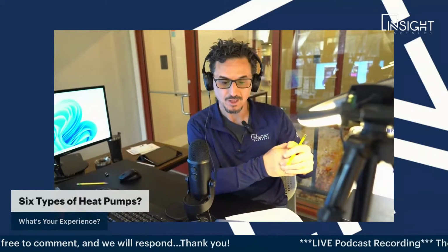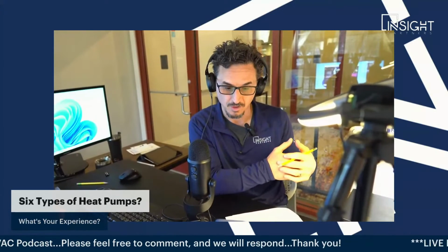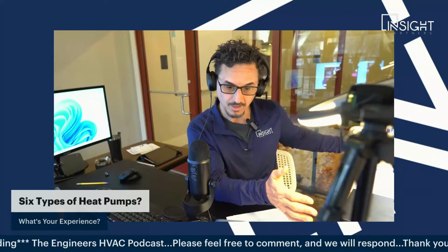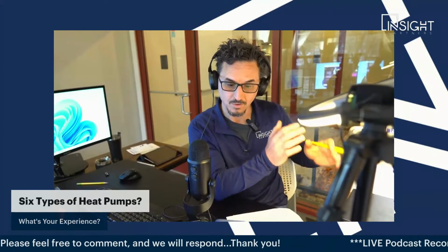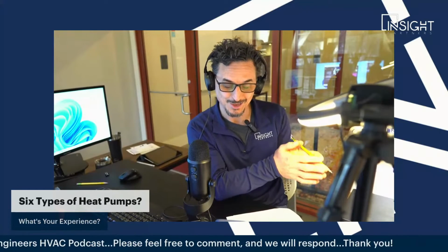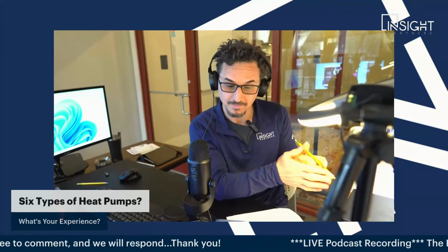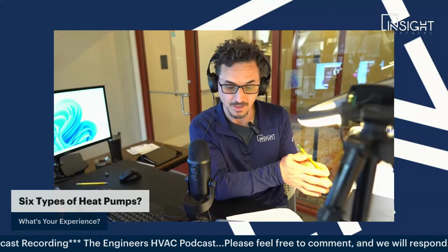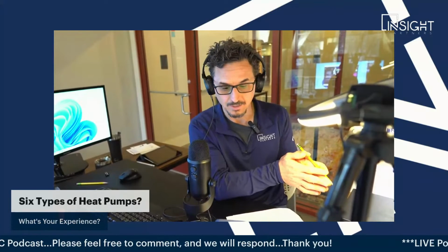VRF systems can be classified as heat recovery or heat pump. This confuses a lot of people because they're both VRF systems. VRF, variable refrigerant flow, just means the refrigerant is varying the flow as it goes throughout the system. In the heat pump version, let's say you had one condensing unit with 20 indoor units—all the units are heating, all the units are cooling, or some could be off, etc. But you can't have simultaneous heating or cooling. So if you're doing a VRF system with a heat pump product, be careful and make sure you understand they can only be in heating or only be in cooling. I'm not really a big fan of that type of VRF system because it doesn't really give you the true individual control you think you're getting when you get a VRF system. So please be careful of that. I did a school once and it wasn't the most ideal situation.